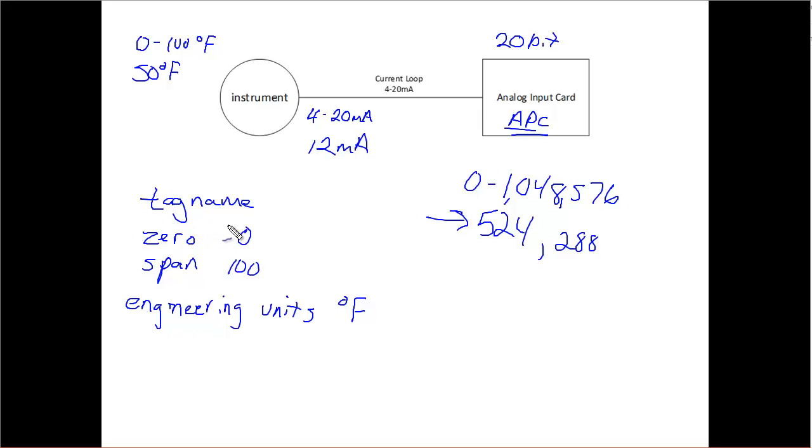When I'm looking at my overall system in my electric grid, this tag name, I should be able to somehow figure out that tag name is coming from this particular analog input card. The zero to 100 tells me what my reading is that I'm taking. My engineering units tells me what the units are here. So if I go to this analog input card, and I look up that tag, and I see this value, I should be able to figure out what temperature I'm reading. Hopefully that's starting to make a little bit of sense to you.